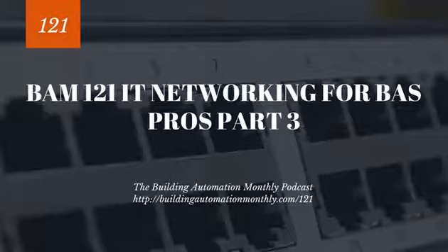BACnet IP, for example, uses a broadcast address. The Who-Is, I-Am, Who-Has, I-Have services are broadcast. They're fire and forget. And it's really important for us to be able to support that. And to do that, we have a broadcast address. That is the address that broadcasts go about utilizing. All right. And then we have a default gateway.